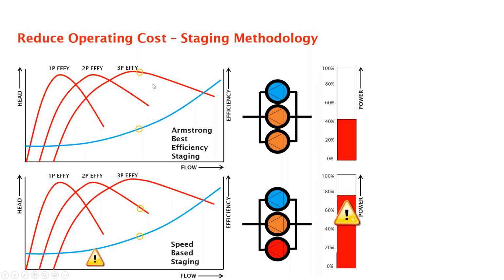The Armstrong pump has brought on the third pump already because it was more efficient to add the third pump into the mix than it was to maintain just two pumps operating. And as you'll see right now, as we continue to go to the total flow that we designed for 100% maximum, here the power ends up coming out to the same, but we know that we work in part load most of the time, so the savings is right there in the evidence on the flow curves.